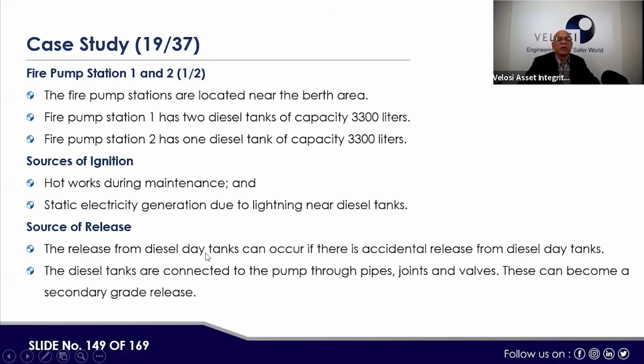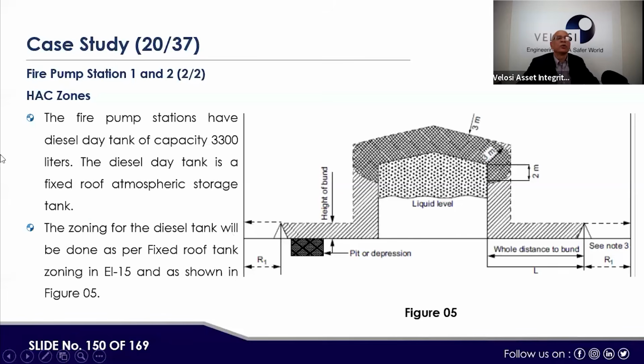Source of release: a release from the diesel day tank can occur if there is an accidental release from the diesel day tanks. The diesel tanks are connected to the pump through pipes, joints, and valves. These can become a secondary grade release. The fire pump station has a diesel day tank with a capacity of 3,300 liters. The diesel day tank is a fixed roof atmospheric tank, and this picture would be applicable. The zoning for the diesel tank will be done as per a fixed roof tank, and zoning in EI-15 is shown in figure 5. This could be an example taken from this.